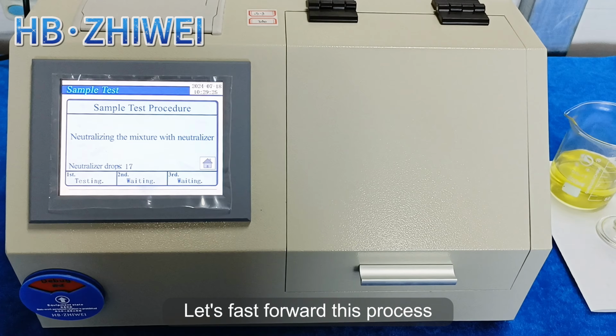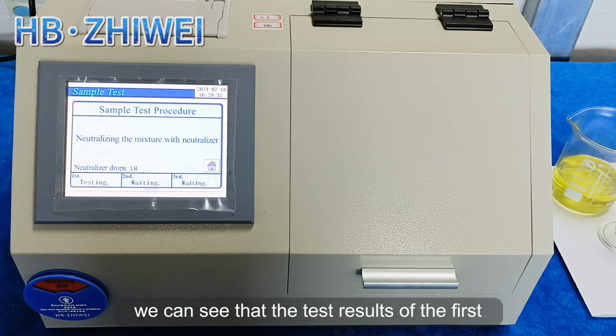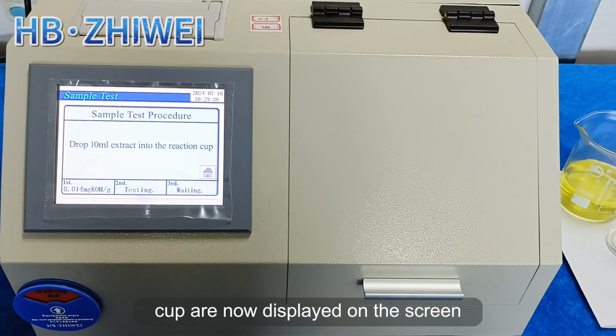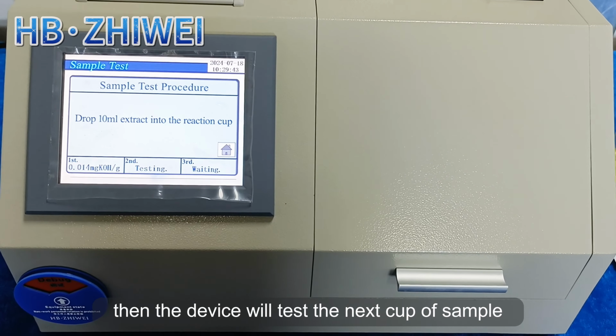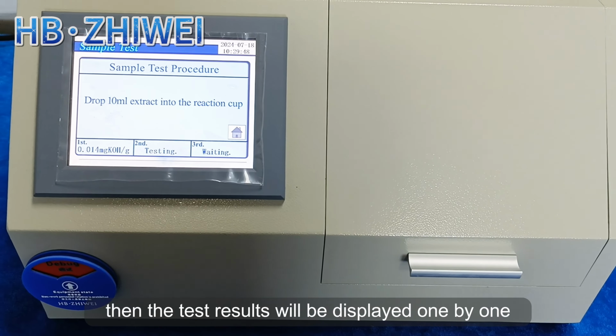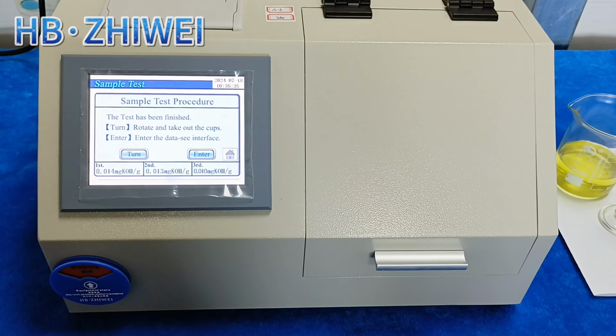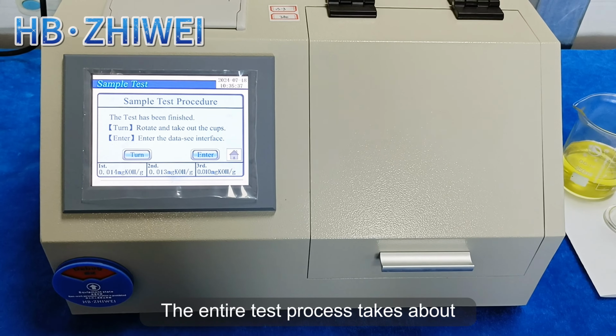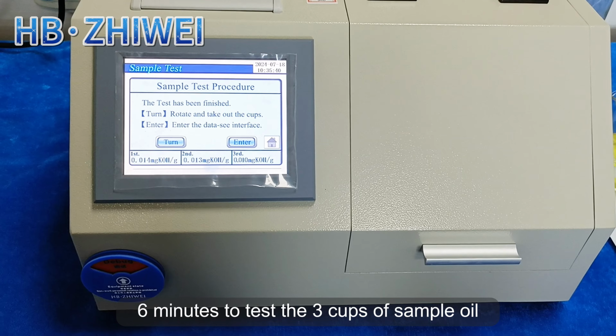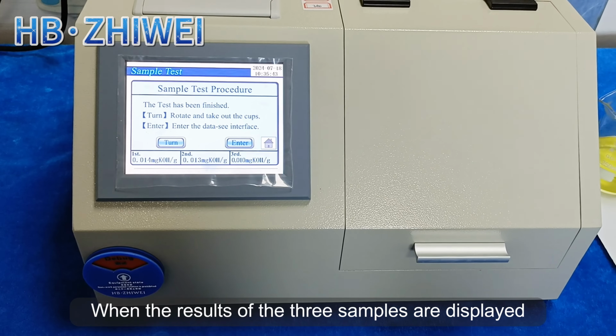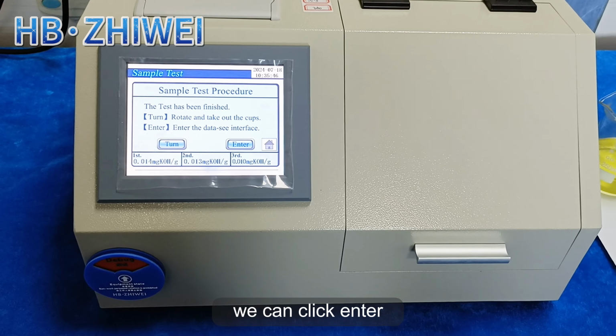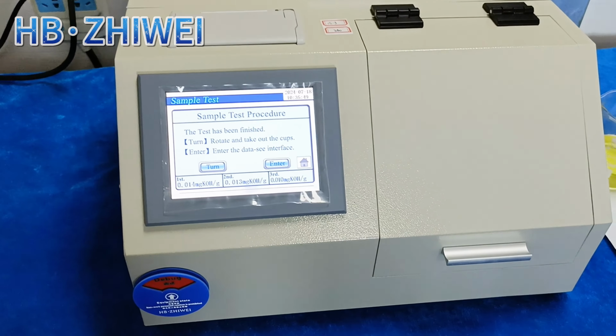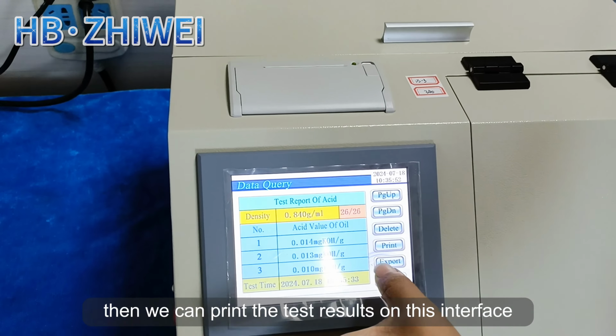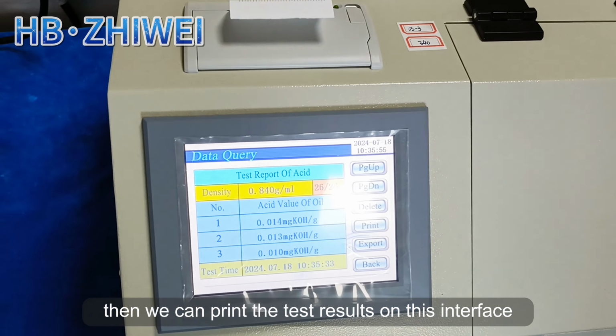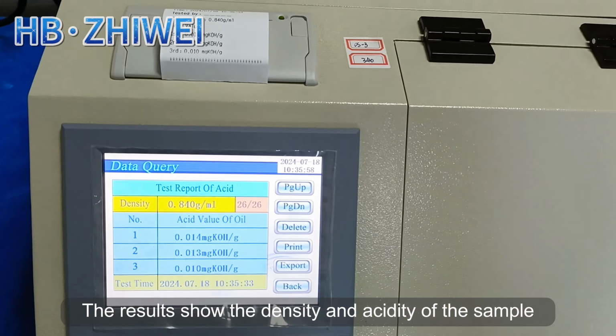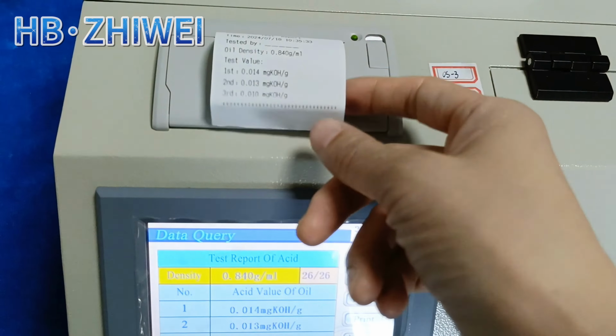Let's fast forward this process. We can see that the test results of the first cup are now displayed on the screen. Then the device will test the next cup of sample. Then the test results will be displayed one by one. The entire test process takes about 6 minutes to test the 3 cups of sample oil. When the results of the 3 samples are displayed, we can click Enter. Then we can print the test results on this interface. The results show the density and acidity of the sample.